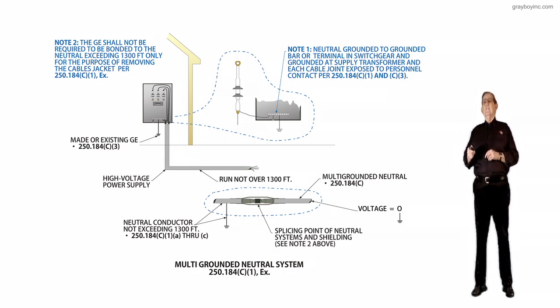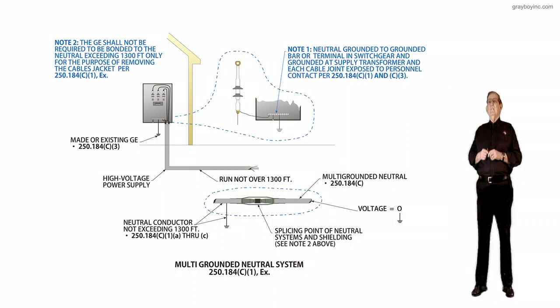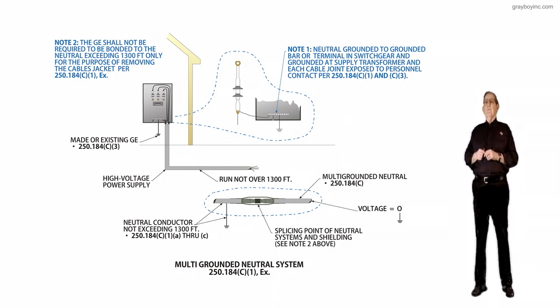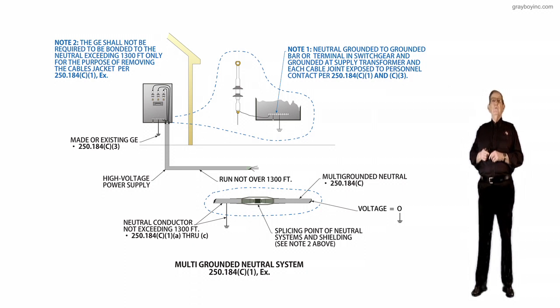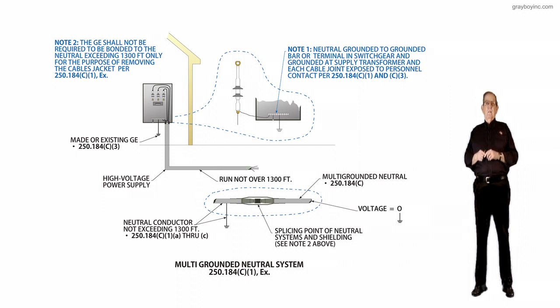If we look at note 1, it says the neutral is grounded to the grounded bar or terminal in the switchgear and grounded at the supply transformer and each cable joint exposed to personal contact, 250.184(C)(1) and (C)(3). Note 2, the grounding electrode shall not be required to be bonded to the neutral exceeding the 1,300 feet, only for the purpose of removing the cable jacket, for 250.184(C)(1) exception. And I think the reason the utility's doing this is that people were making these splices, electricians and so forth, that really weren't qualified to make them, and they created problems for the utility. That's my opinion. But this was the main reason for this new exception and the purpose of change.